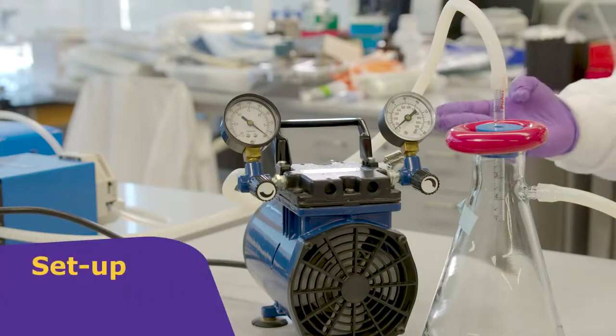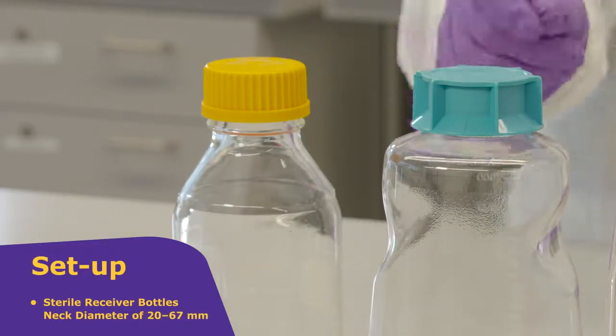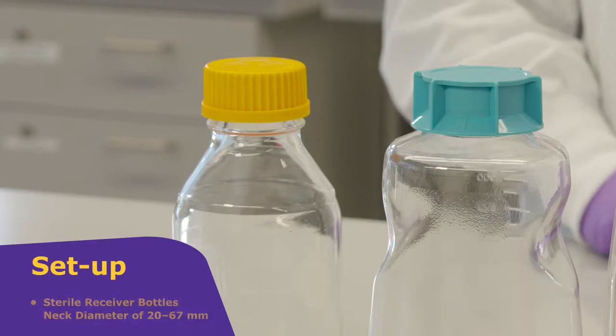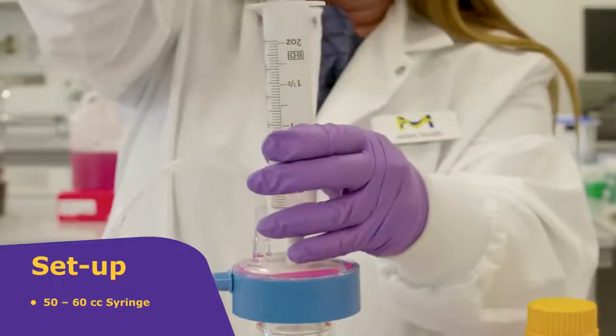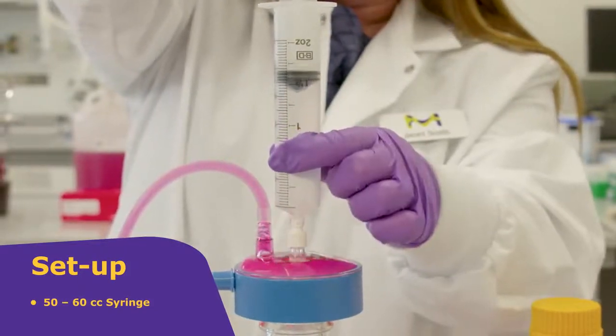Setup: You will need a regulated vacuum source with tubing, sterile receiver bottles or vessels with an inner neck diameter of 20 to 67 millimeters, and a 50 to 60 cc syringe that can be used to reprime in the event of air locking.